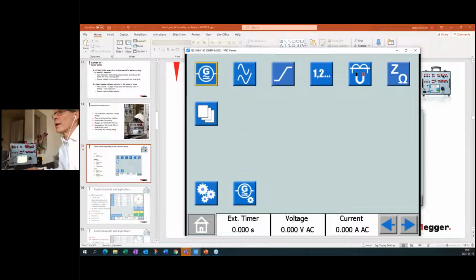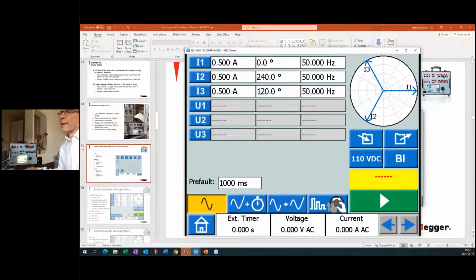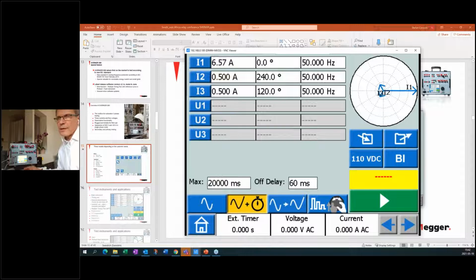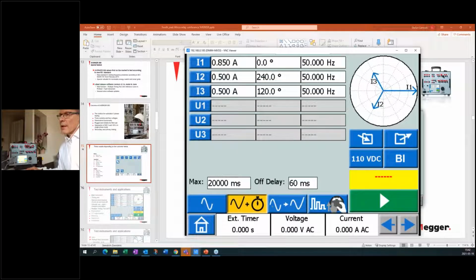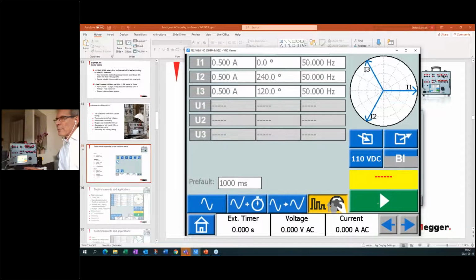Next step, I would like to show you if you would like to take several test points in the same test and save it and have a nice graph and so on, you can use the pre-fault fault instrument. And I activate the pre-fault fault instrument now. Here I do the setting for the pre-fault, how long I would like to stay in the pre-fault setting. I do the setting for the fault setting. In this case, we start at 0.85. So I do the setting for that. And when I would like to have several test points saved in the same test and have a graph, I'm using the new function we released last year. We call it multiple timing test. And then you will actually use the knob here to do the tests. So I activate the multiple timing test, and I press the play button.